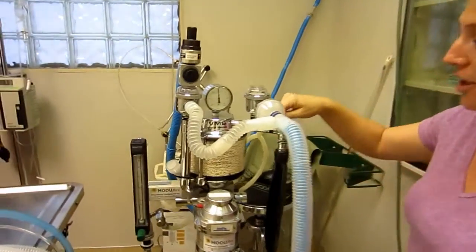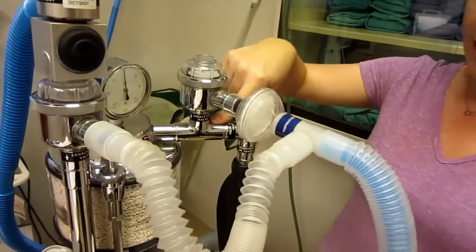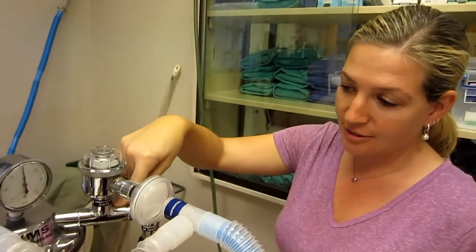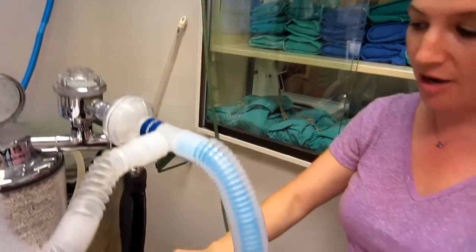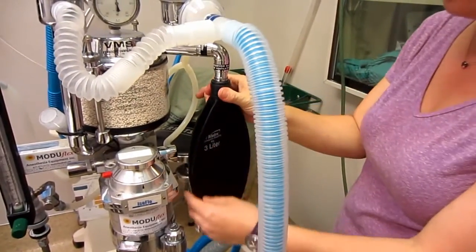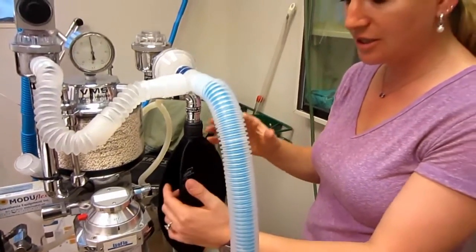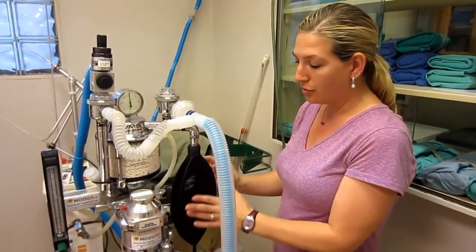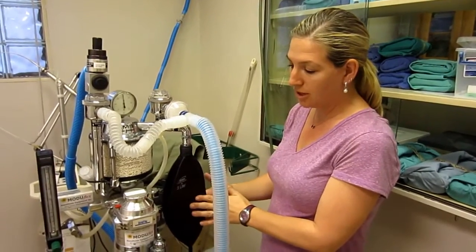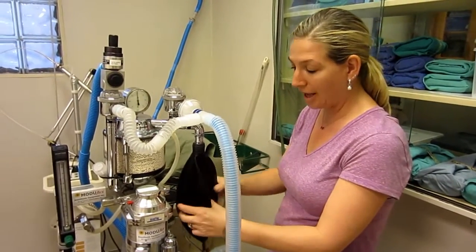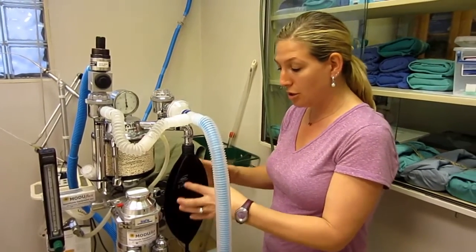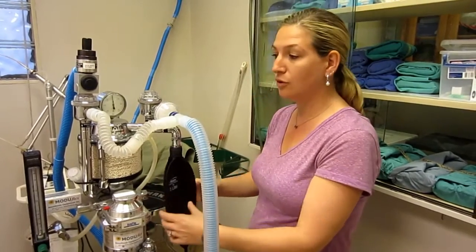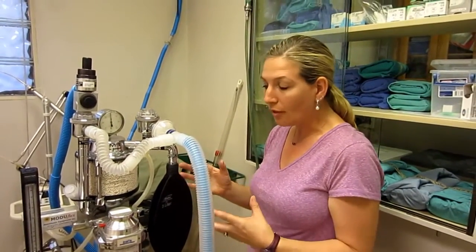Okay. So the oxygen picks up the isoflurane and comes out the outlet port right here and goes up this tubing, and so now it's oxygen and isoflurane gas, or anesthetic, mixed together, and it's going to go 2 places. One is going to be the reservoir bag, which comes down here and mixes in, and this bag gets filled slightly with air. There's a few functions for this.